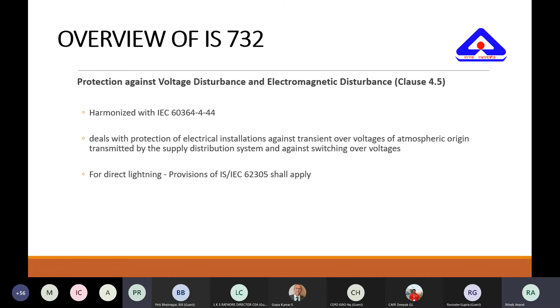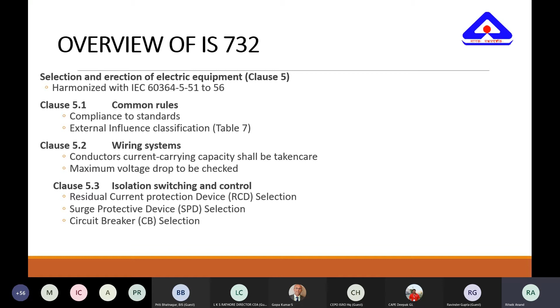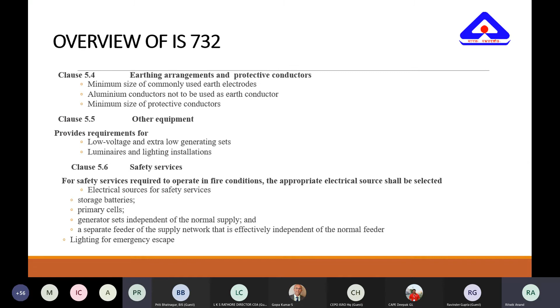Then there are measures related to selection and erection of equipment, which are given in clause 5 of that standard. In that, there is a method for how to select a device, how to select wiring, cable sizing, and RCD and SPD selection. These are given in the standard. Clause 6 of the standard covers the verification, which covers the various kinds of tests that are required to be done. It covers both initial verification and periodic verification.